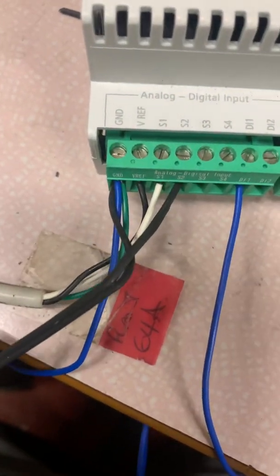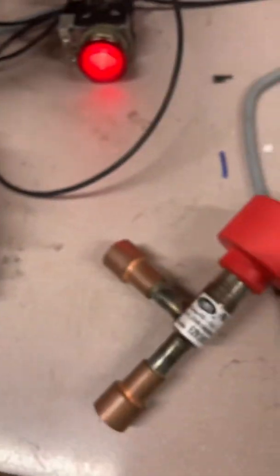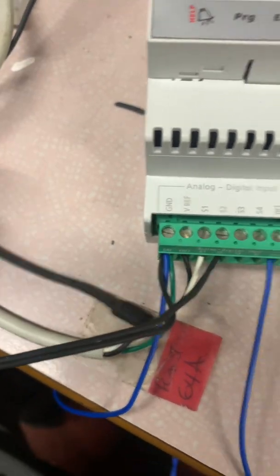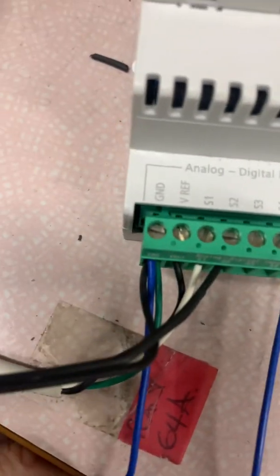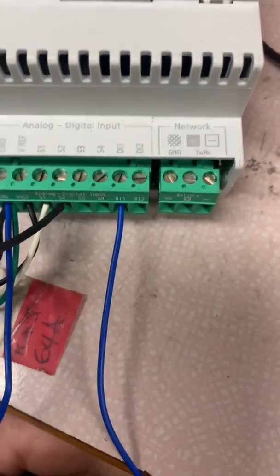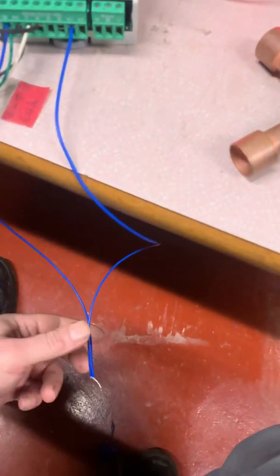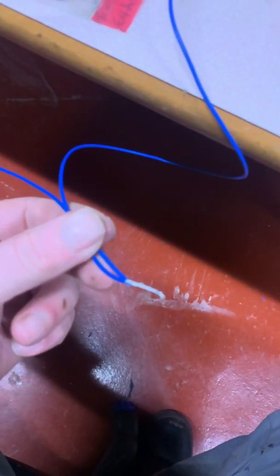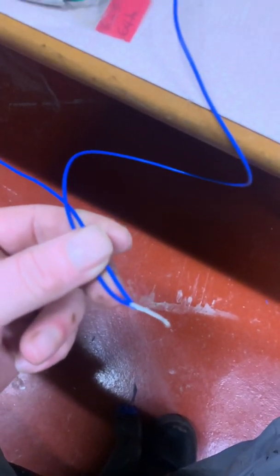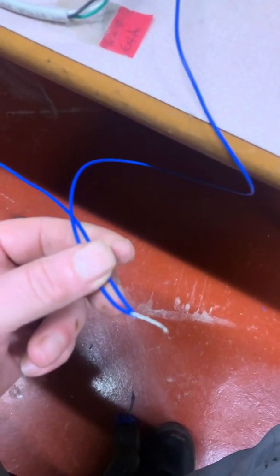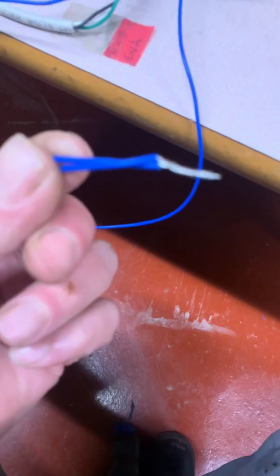Then your second probe, as they call it, S2, is your Carel 10K probe. And then the next one you have to be aware of is the digital input. So you come from ground to digital input, and I've just got a wire in here, and that's going to be your command to tell it to go. Now I'd have that coming from your refrigeration controller. So what would normally energise your solenoid, I'd have that switch, I'd have put that in.